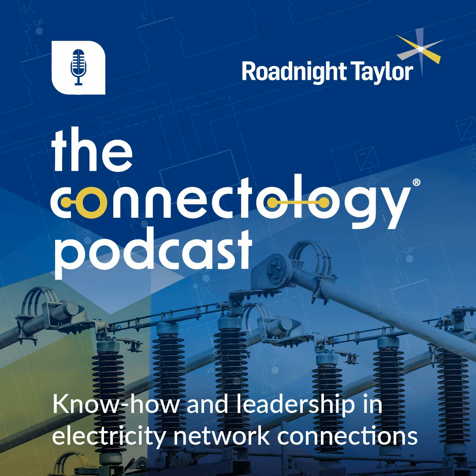And then it can get even worse still, whereby you're not physically tripped off for an outage of something that you're connected to, but if some other asset in the substation gets tripped off or gets switched out, you will just be turned off, because what National Grid will have modelled is that if one of the other transformers in the substation is switched out, you have to be switched out as well, just because of capacity issues. And this isn't just hypothetical. We've done due diligence work for developers and looked at these connections for them. And this is the sort of thing that we're seeing on some of these offers that have come through. So some of them have got quite high risks associated with them. So that's the main one, really around the constraints.